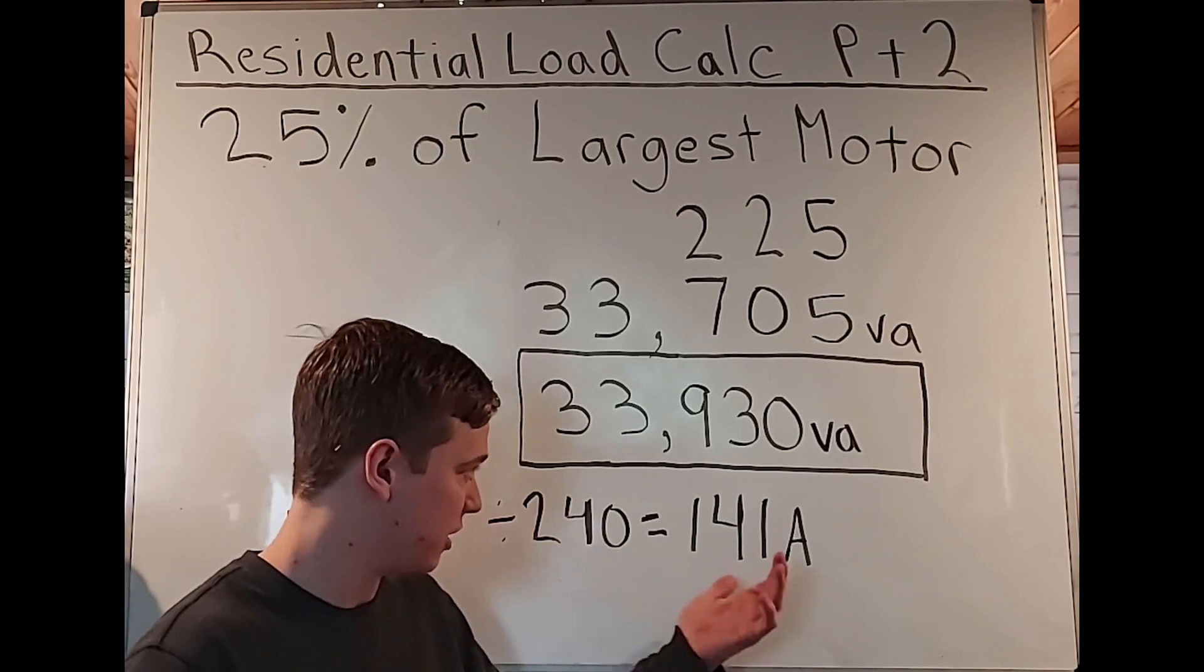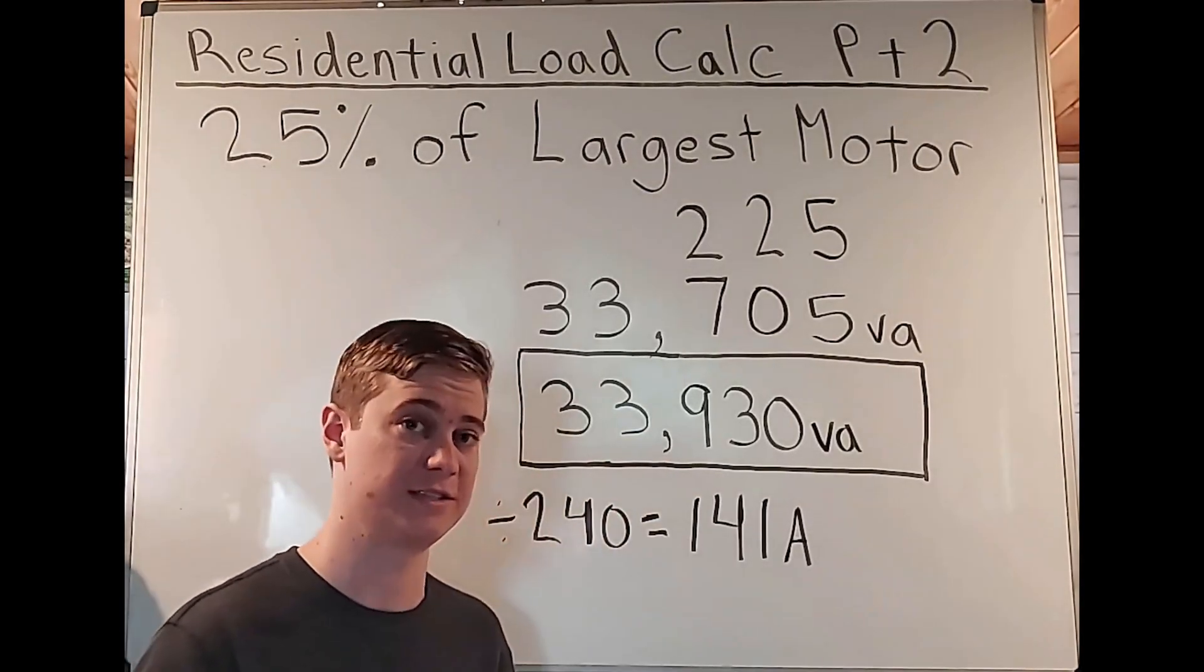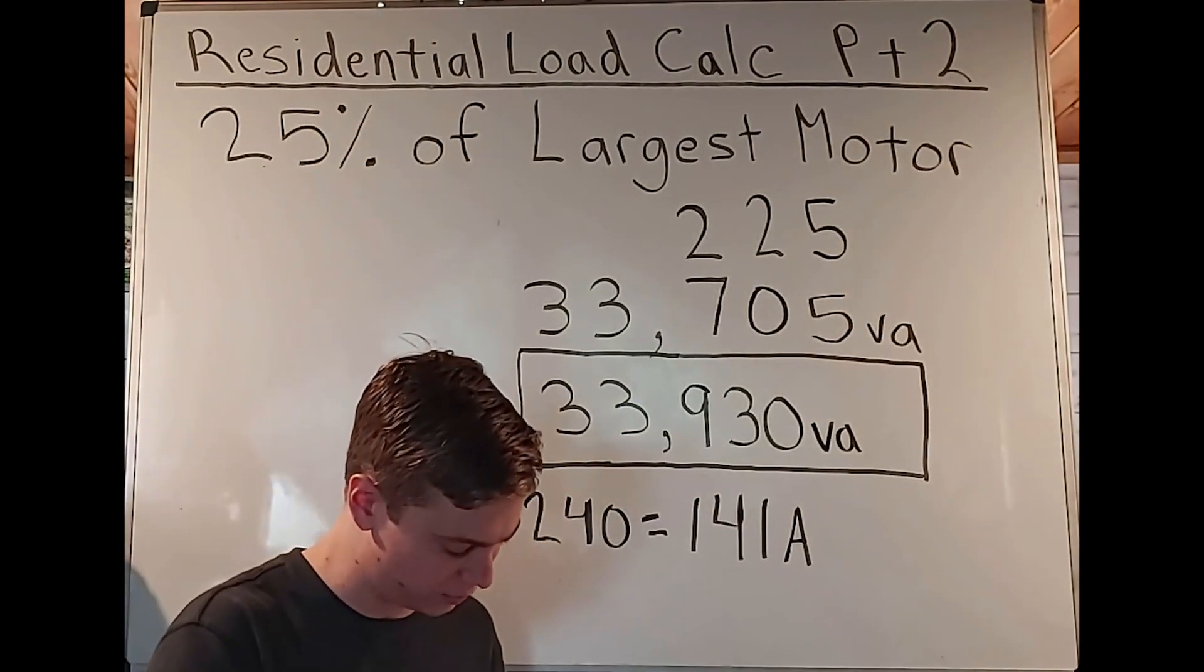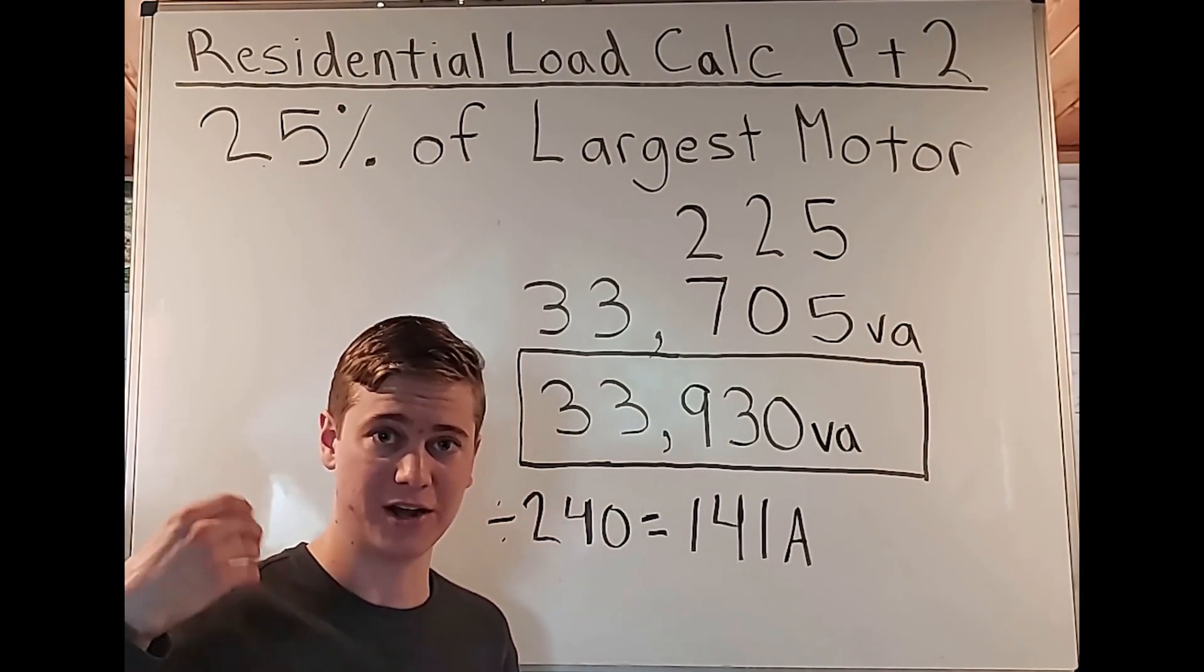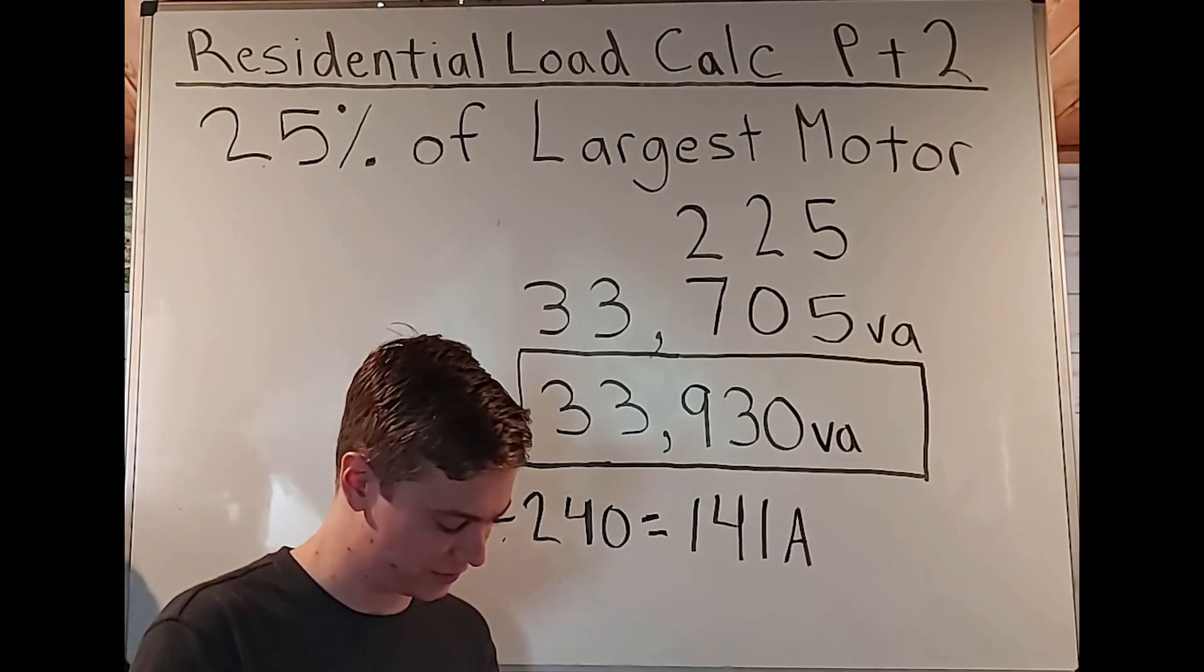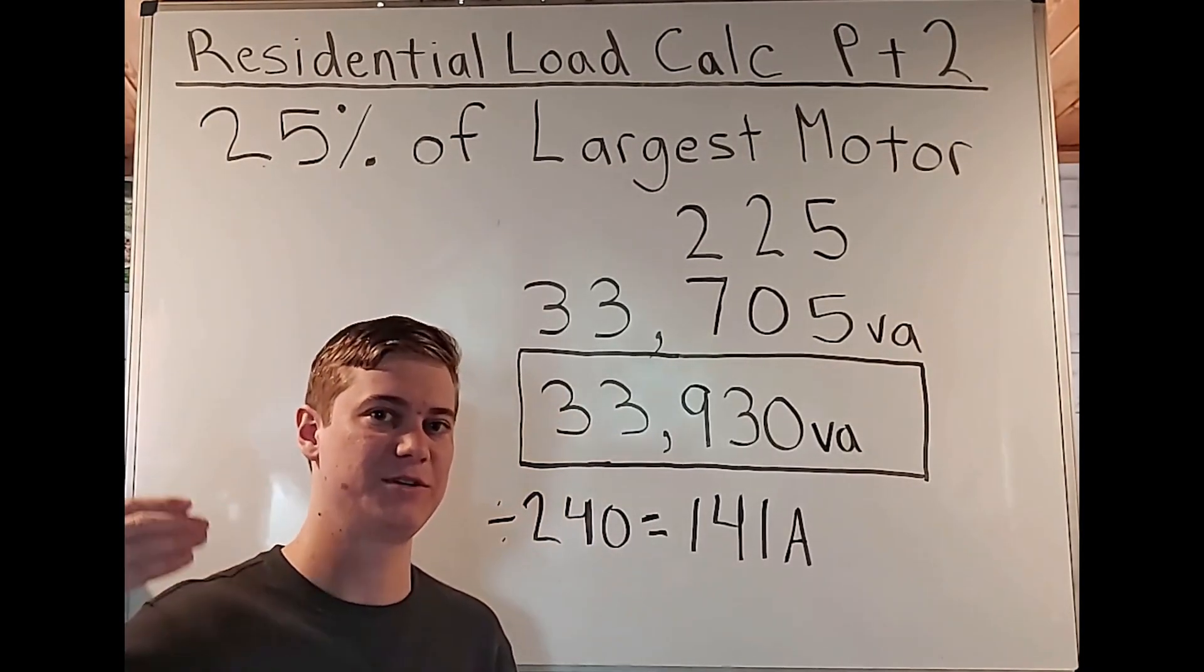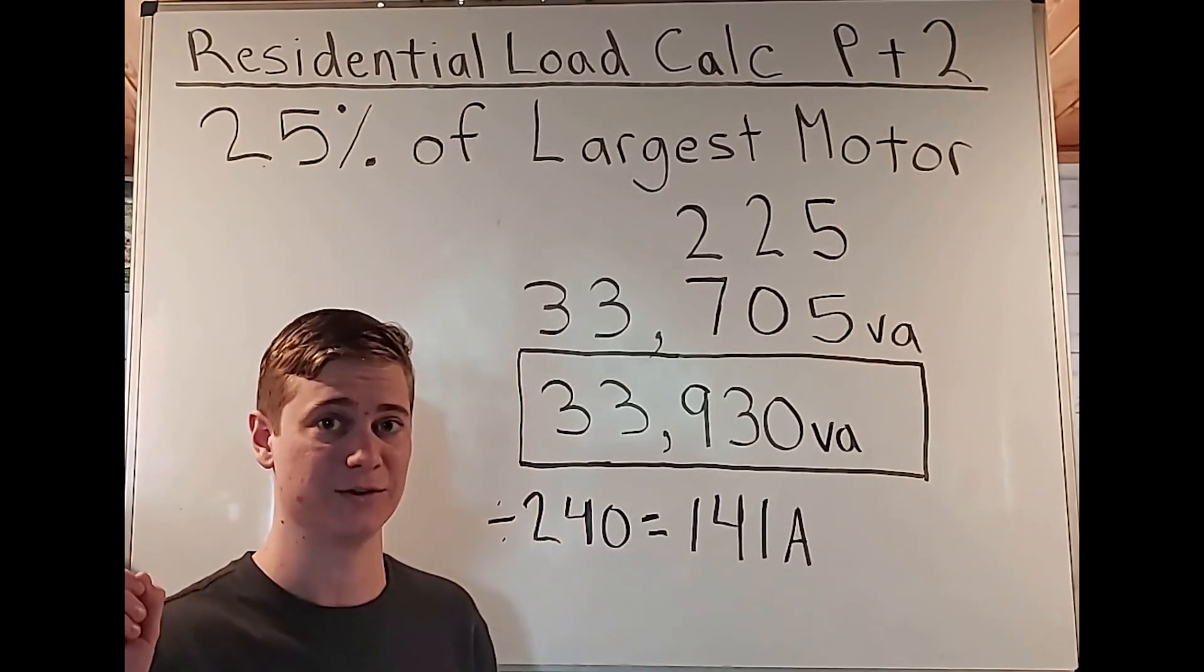And again, I keep saying it, but that's if it's not exceeding 800 amperes. So let's go over that one more time. I found my amps for my house. I'm going to table 240.6A and I see 125 and 150. Now there's no mention about the conductors being a part of some branch circuit supplying an outlet that's kind of specific.